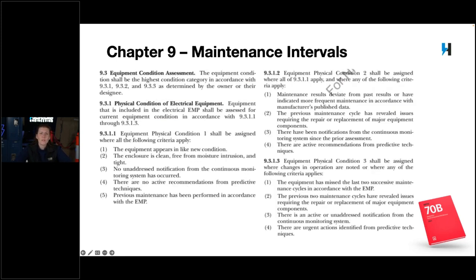Let's go back to those equipment condition assessment specifications. Condition 1 is like new equipment - you've kept up on its maintenance, there's been no problems, no moisture, nothing's been damaged, and you've performed the maintenance required per the codes and standards and the manufacturer's requirements. That's condition 1. So every year you're good to go - do your annual scan just to make sure it's still in good shape.